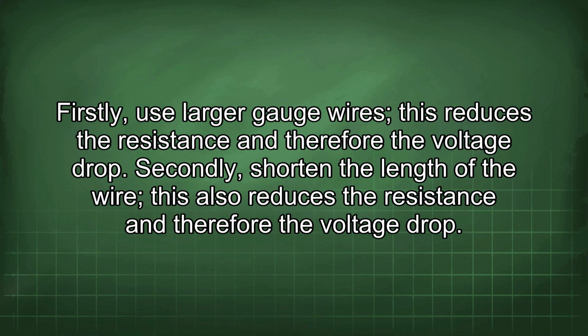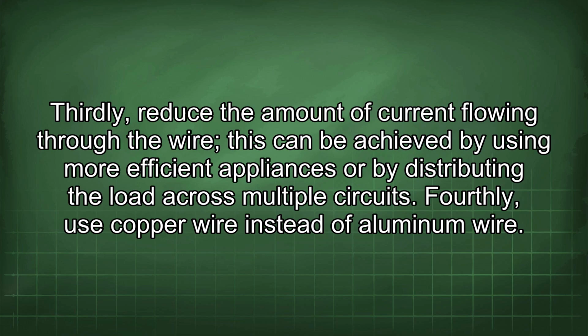Secondly, shorten the length of the wire. This also reduces the resistance and therefore the voltage drop. Thirdly, reduce the amount of current flowing through the wire. This can be achieved by using more efficient appliances or by distributing the load across multiple circuits. Fourthly, use copper wire instead of aluminum wire.